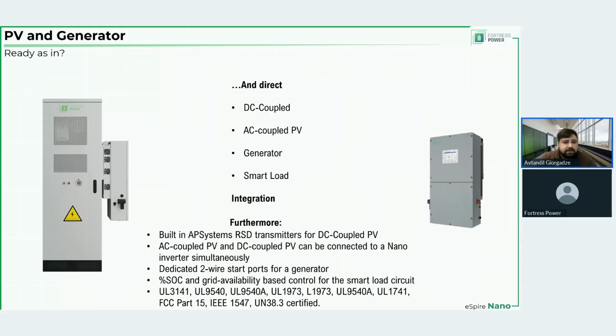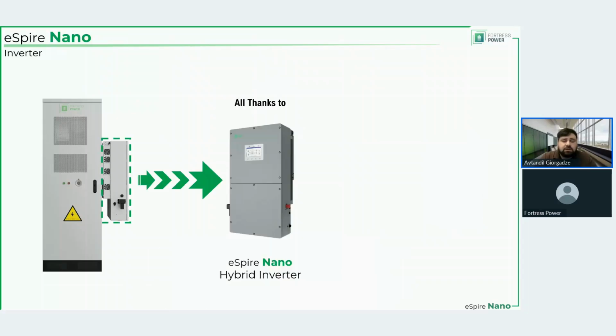Either of these three. For the generator, it has also 2-wire start ports, and you can program the inverter to turn on the generator based on a certain state of charge of the battery. And obviously, we have all the relevant certifications, as you can see here. This is all due to the inverter and its capabilities, because if you really think about it, the purpose of the battery is to provide energy and store energy, but the inverter is actually what allows the system to interconnect with the rest of the world.